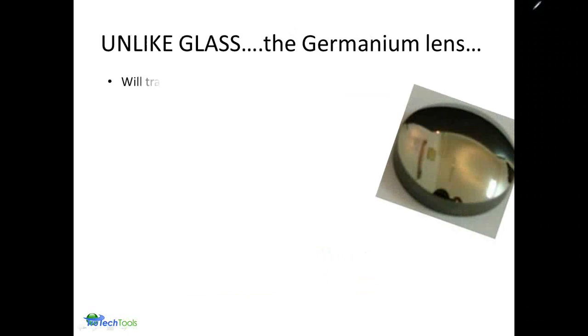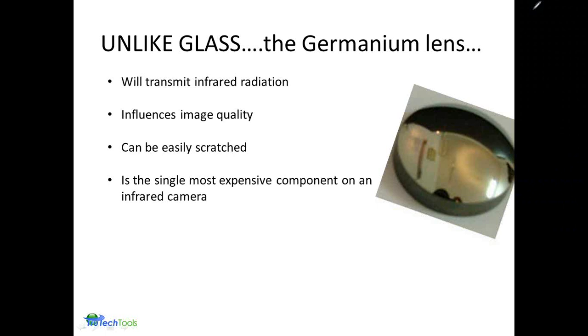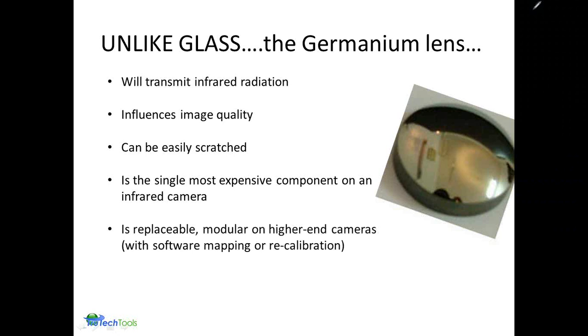Unlike glass, the lens of your camera, many are made out of germanium, will transmit infrared radiation through the material. The lens is probably one of the single most expensive components on your camera. It can be easily scratched. There is a coating on there that only allows a certain wavelength through, specifically about 8 to 14 micron, allowing the quality of the image to be as good as it can. Being expensive, you don't want to be rubbing or scratching it with any regularity at all. Replacement is fairly expensive, so protecting it with the lens cover and certainly not exposing it to harsh chemicals or abrasive materials is very important.